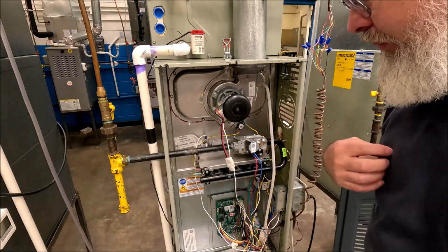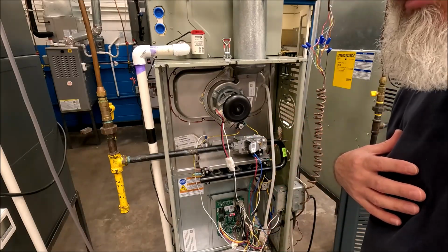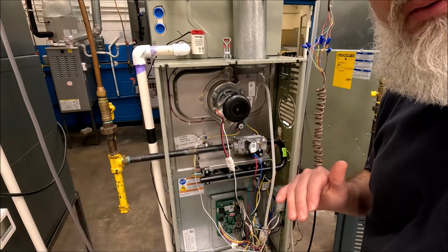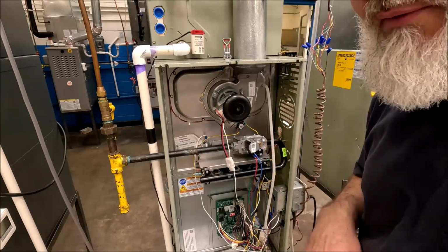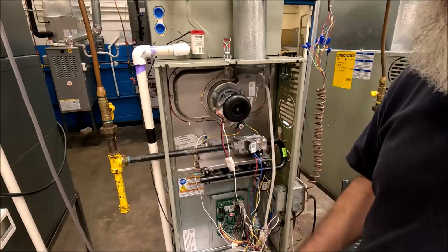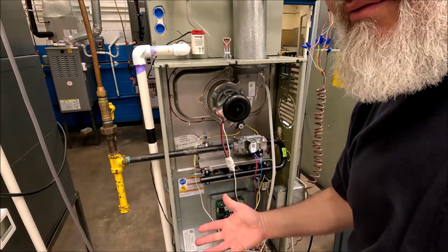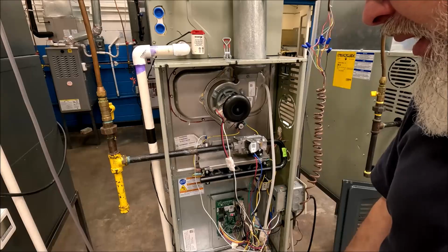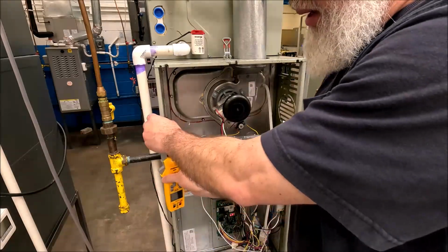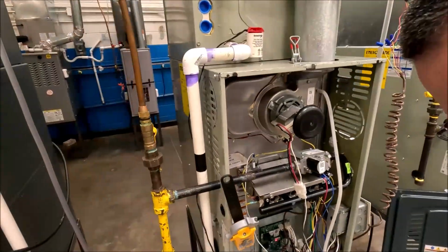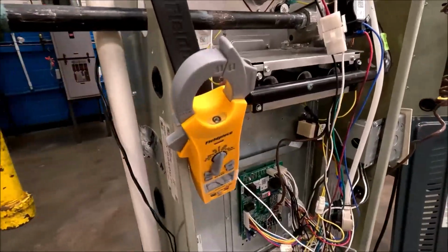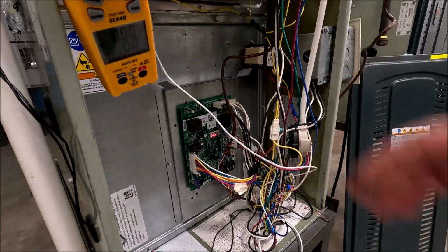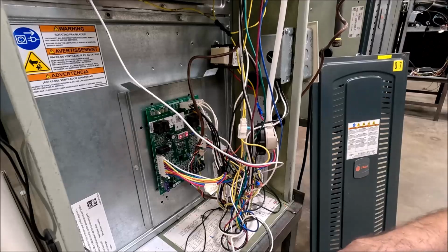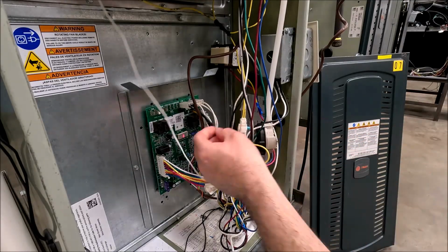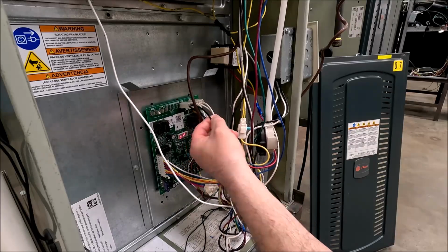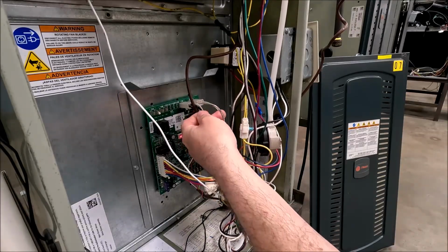So X13 style motor, if you've done any homework on those, you know that they always have a constant high voltage power source. It's on 24/7, 365 as long as the power to the whole unit's on. Even though it's not running actively, it still has high voltage power on it. So as we read the diagram to find out where the connection is, which is good, you would find that it actually gets its power from L1 and neutral all the time.